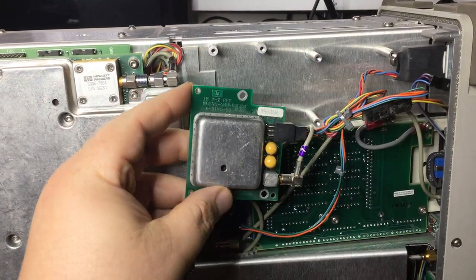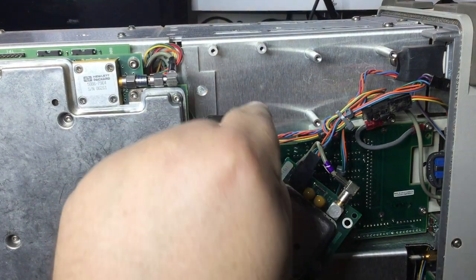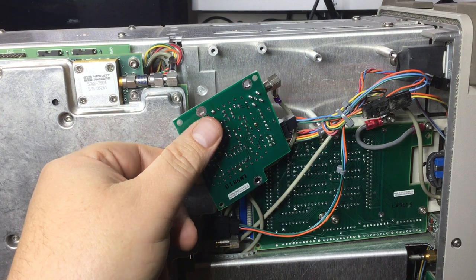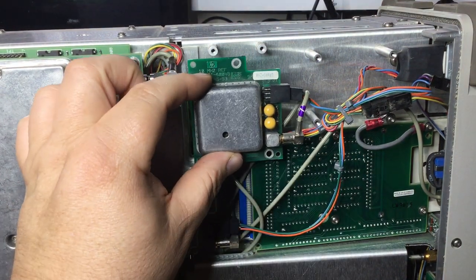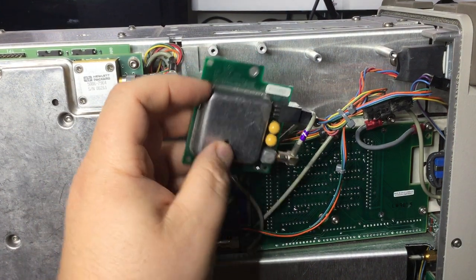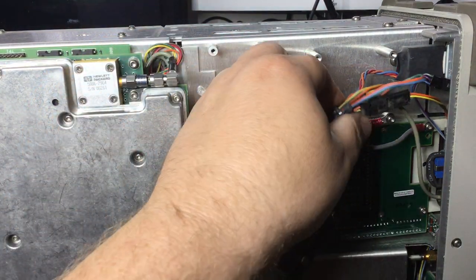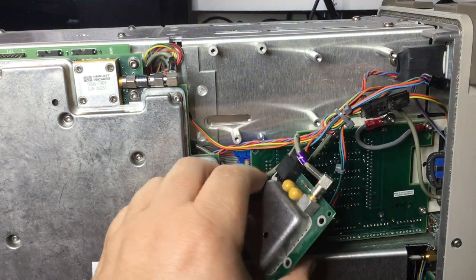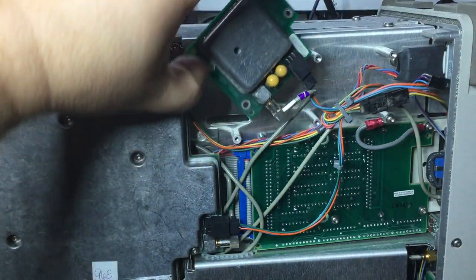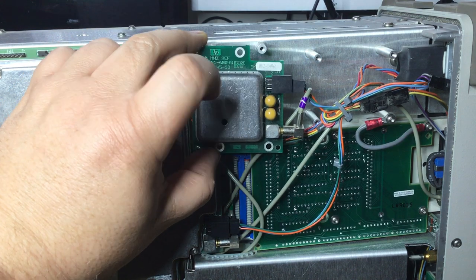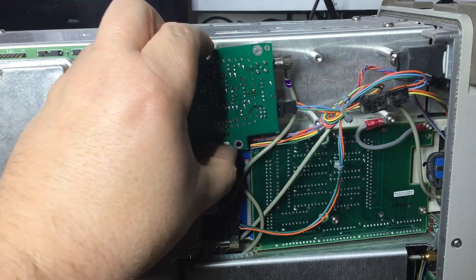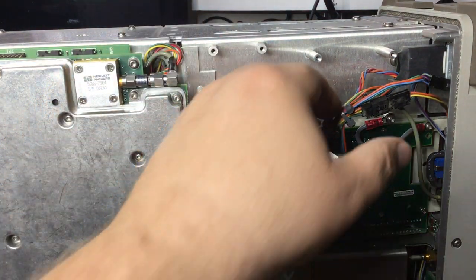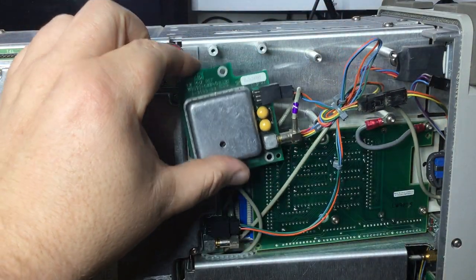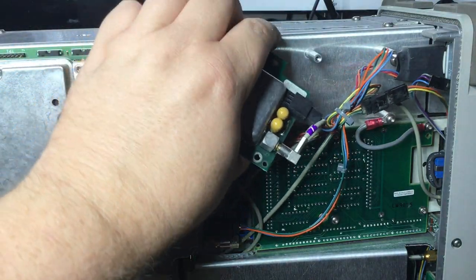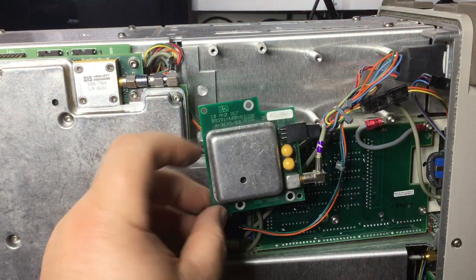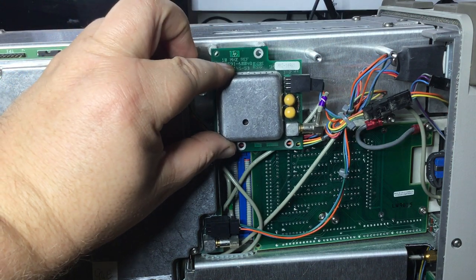One of the other possibilities that I was looking at is that the service manual gives reference to an adjustment being made from this side, with it being fitted like that. I had thought that perhaps when Agilent had a go at it, if they rushed to put it back together, they put the module in the wrong way around when it should be this way. So obviously it would be in synergy with the service manual showing an adjustment from the bottom of the instrument. But I can clearly see that the cables, although they are cable tied here, I'm not sure whether the module would be in that way, if you see where I'm coming from. But it would be bolted like that, and then you can adjust it from underneath. But the cables don't seem to reach, so I think it is meant to be in that way as well. But I'm not sure. There's plenty of cable here, and perhaps that's where it was meant to be mounted. Although the pillars underneath seem to indicate that it could potentially be mounted that way, because they would line up, or would they? No, they wouldn't.